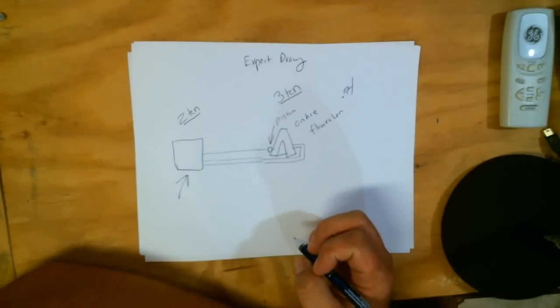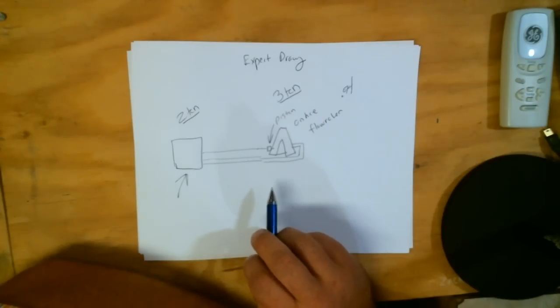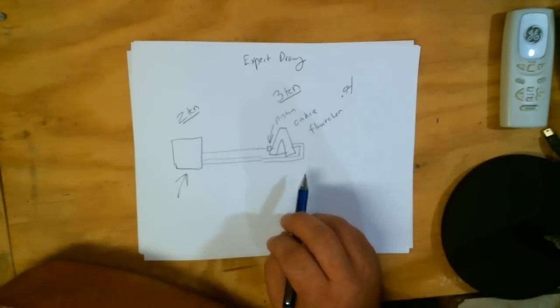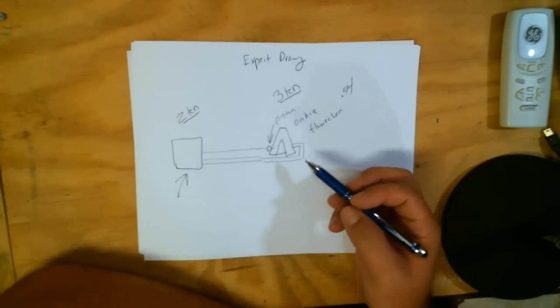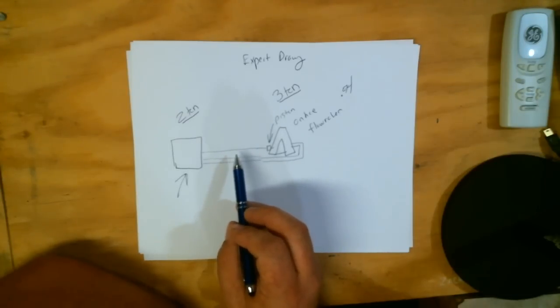For those of you guys out there, make sure you love your wife and always answer her text. I hope she's listening. So if your piston is oversized, what's going to happen is it's going to allow more liquid through into the evaporator coil. That's going to have a tendency to flood the coil, lower the superheat, and in turn you're not going to have as much refrigerant stacked over here in this section of the liquid line, so your sub-cooling is going to go down.